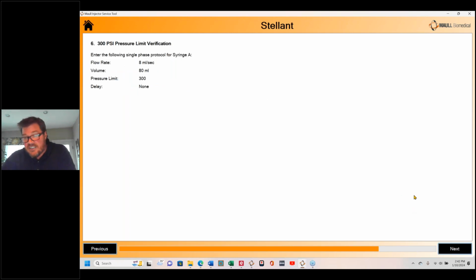So now we're doing pressure limit checks. Like I mentioned earlier, pressure limit is not a difficult concept, but it takes a few minutes to explain, so I won't go into it. The pressure limit is basically the maximum pressure allowed to build up in the syringe during the actual injection. If the injector tries to exceed that, the system will react to it. It'll throw up an error, and it will adjust the injection accordingly. So we're setting up a flow rate of 8 milliliters per second, a volume of 80 milliliters, and we're going to select a pressure limit of 300 psi.